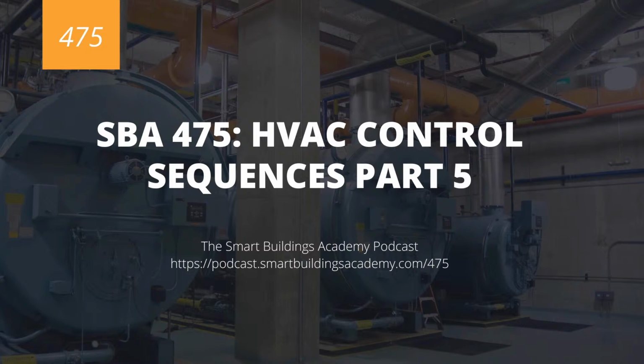And then finally, hot water set point. Sometimes we're able to do that. Sometimes we're not. Sometimes that'll be done by controlling the firing rate of the boiler. Sometimes that'll just be a 2-wire control set point. And sometimes that'll be like a BACnet or Modbus interface card. But there's multiple different ways of controlling that.